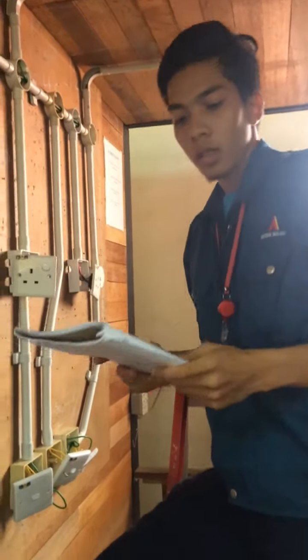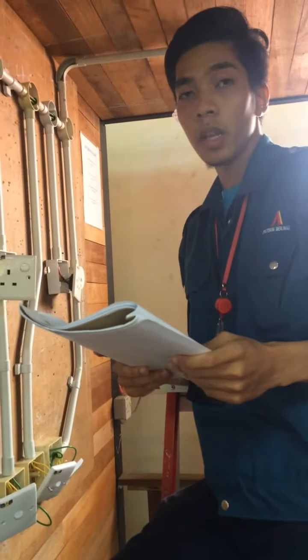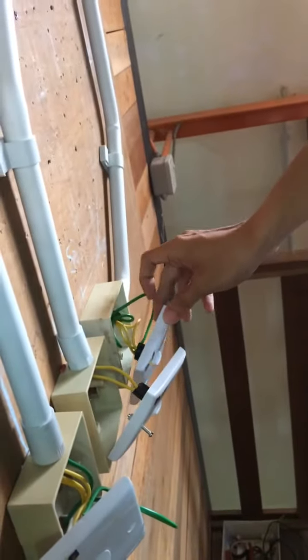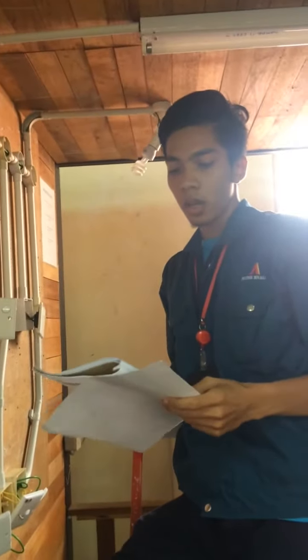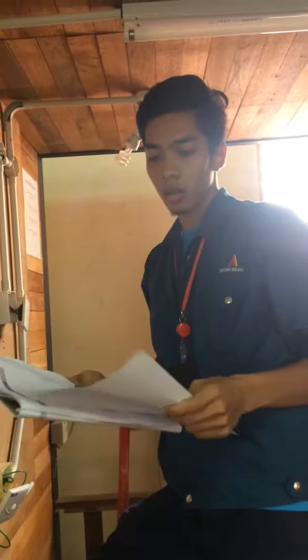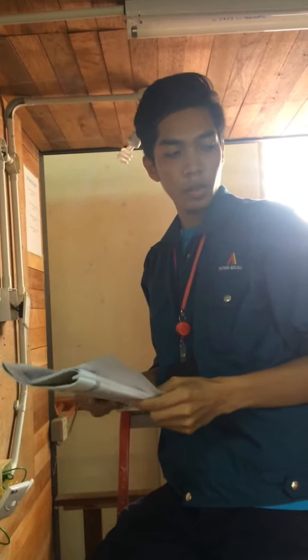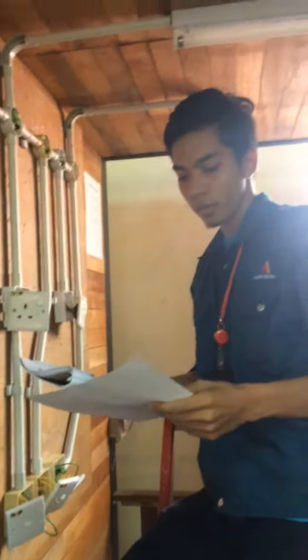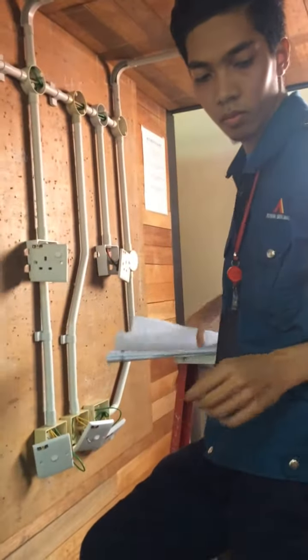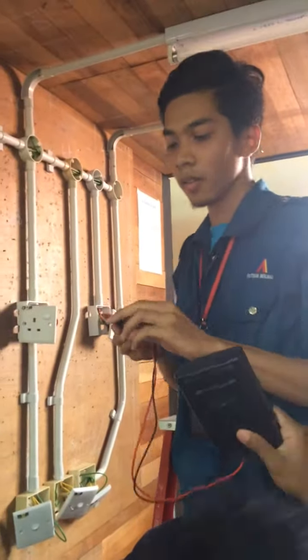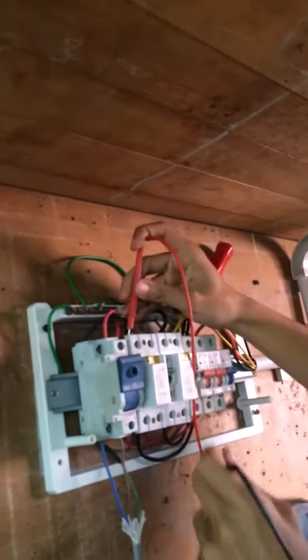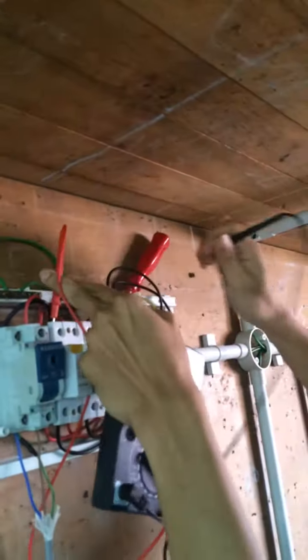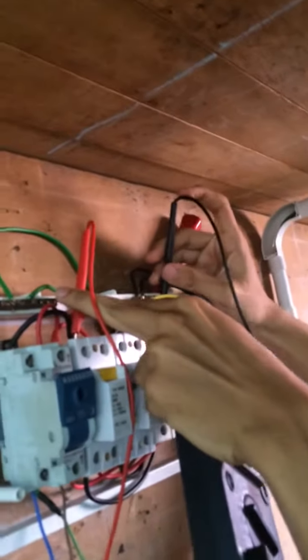Okay. First, create the temporary connection between earth terminal and live terminal at the switch point. Here, switch 1. Here, switch 3 and the load. And then, let's start the test.